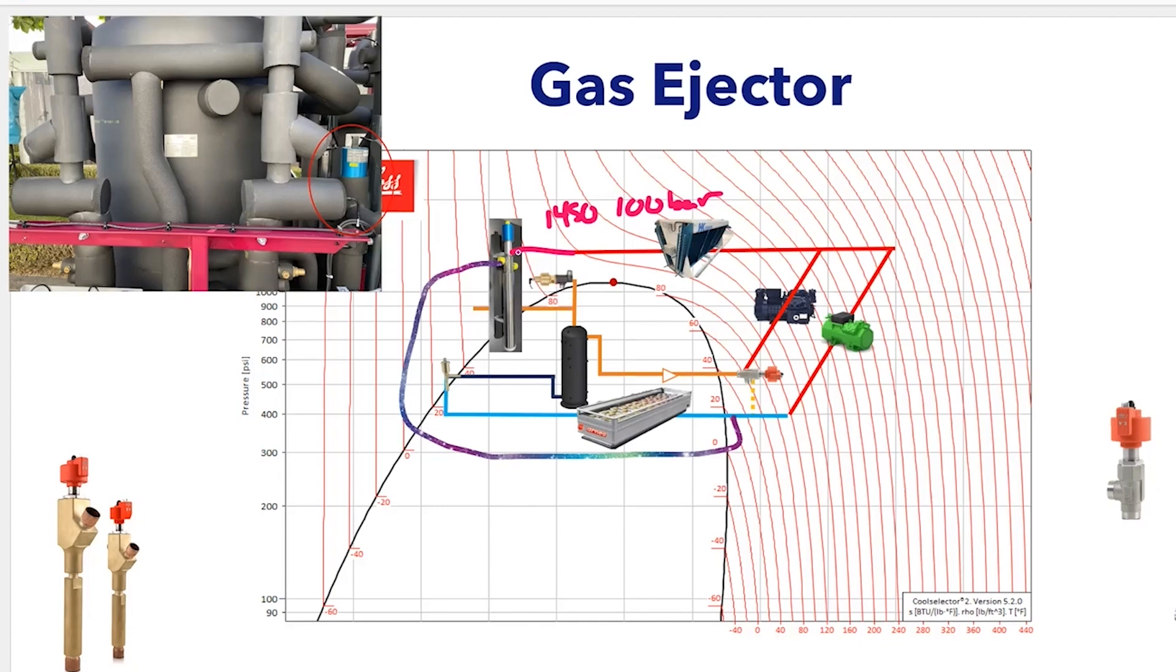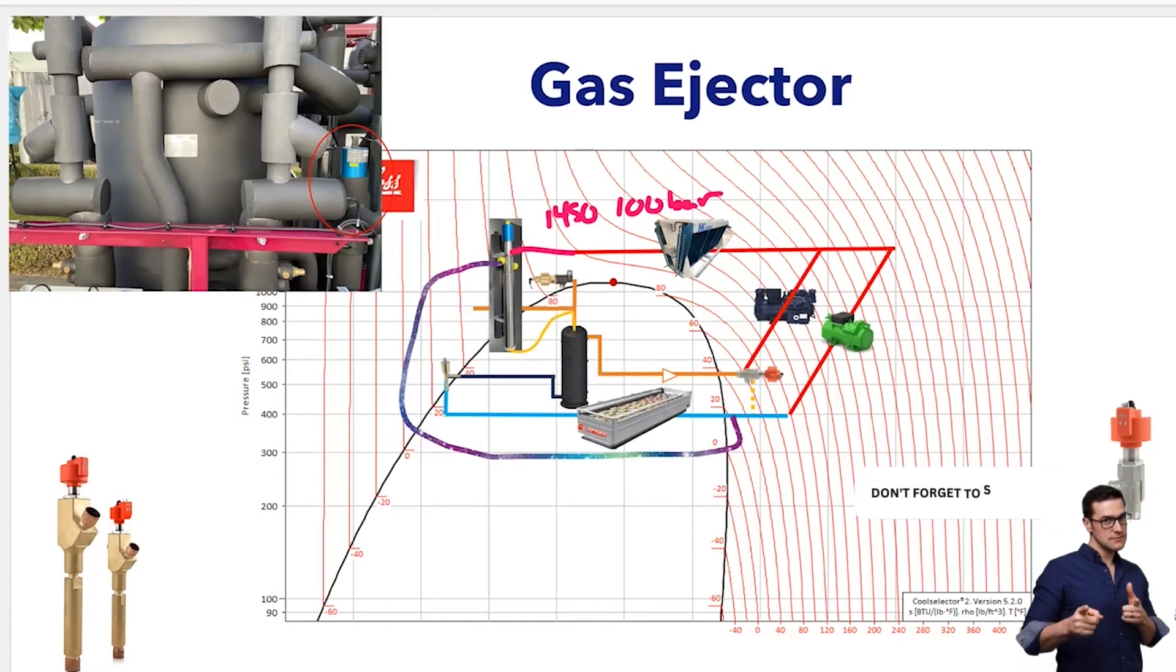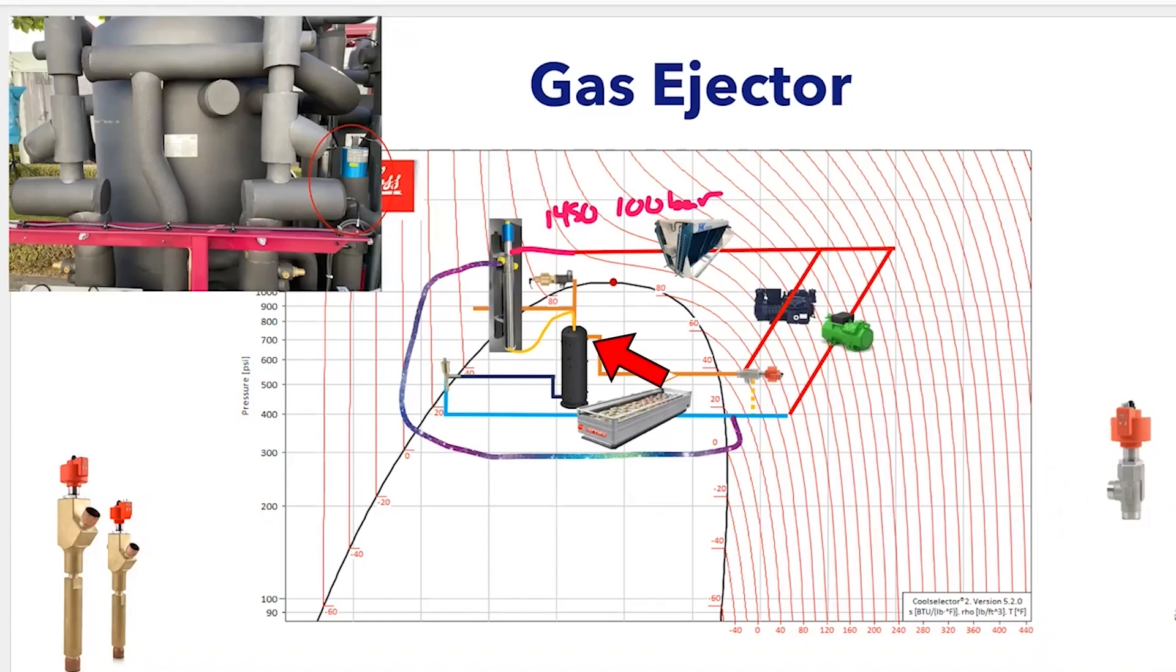I have high pressure gas going into this ejector. It's in a Venturi style. You get this high pressure gas going through, which is actually sucking up this medium temp suction vapor. From this, it goes into the flash tank. Now, instead of this medium temp gas going back to the medium temp transcritical compressors, it's going into the flash tank and up into the parallel compressors.